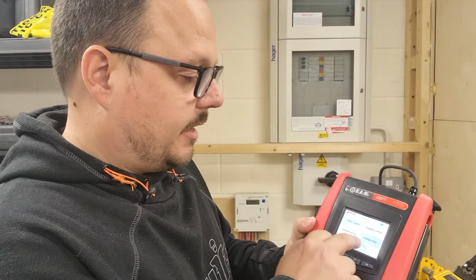And if we go into leakage current, it shows you there that you need to connect the probe. So while we're on with that, I'll show you that the probe won't pull out, it's fixed firmly, and there's a little release lever that you need to push. And you can see on there, there's quite 3 small pins in there. And I think that's been designed in this way because you don't want to be damaging them, so it locks itself in nice and tight on there, so you're not going to be ruining the lead. I mean, this accessory is, you know, it's a considerable expense. It's not something that you're going to want to be getting damaged, so it's good that there's been a bit of thought in the connector there.